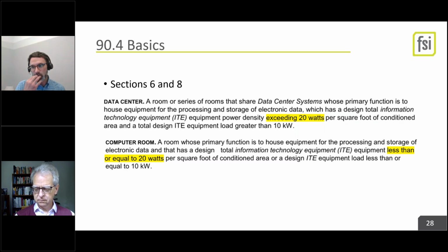It's worth saying that 90.4 changes how we measure power, and it focuses only on HVAC and energy. There's an older metric out there, the power usage effectiveness, the PUE, that doesn't really apply here anymore. So it's worth getting in there if you do data centers, and look at the definition to make sure you do data centers. There's a fair amount that goes into that, but it all comes out to a pretty easy efficiency, electric use per capacity unit.